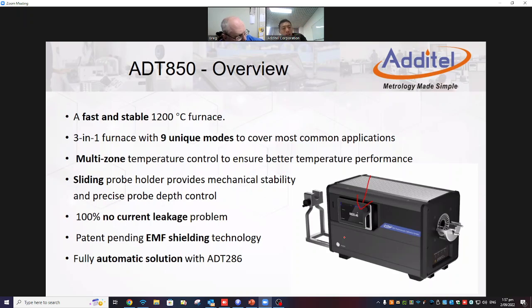One point where the A50 is better than the Fluke one is the cooling time. For the 9118A, I think that's the Fluke one, they may need 3 hours, 180 minutes, to cool down from 1200 degrees Celsius to room temperature. But the A50, I remember it's just 90 minutes. So that's just half the time they need to wait. Okay. Yeah, pretty big advantage.